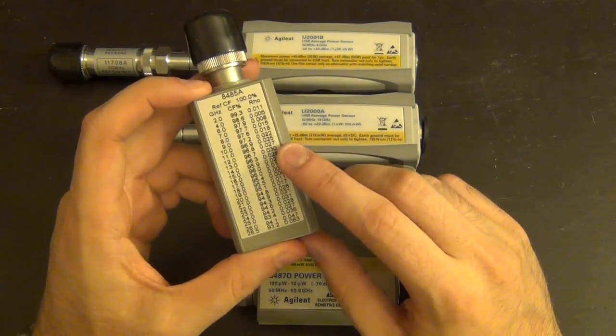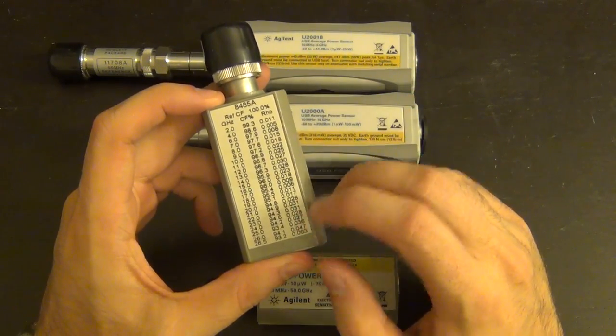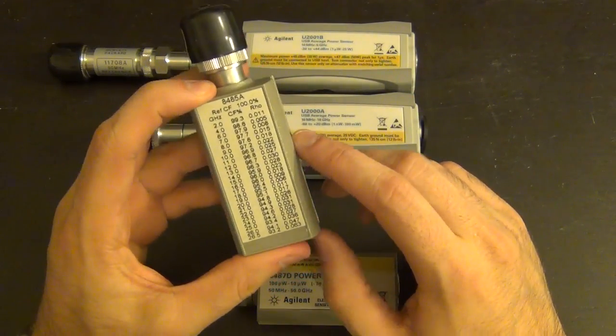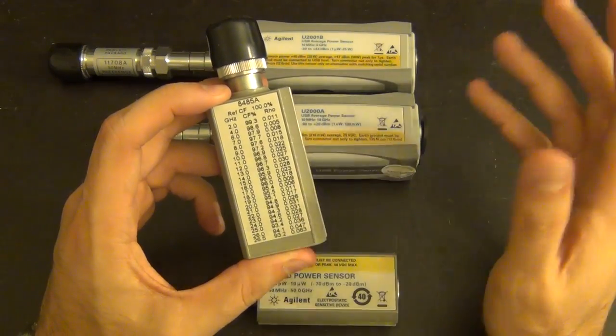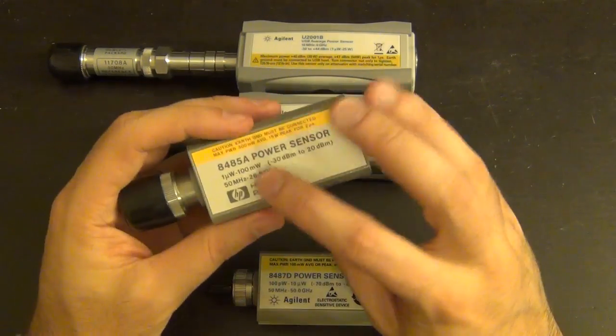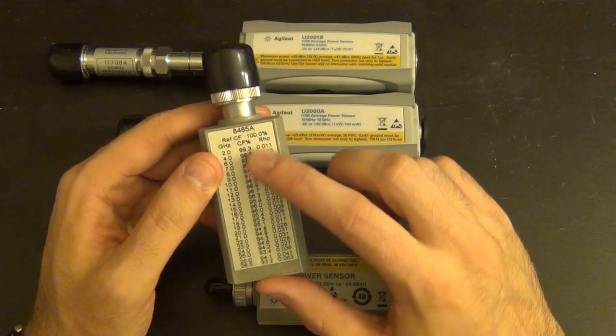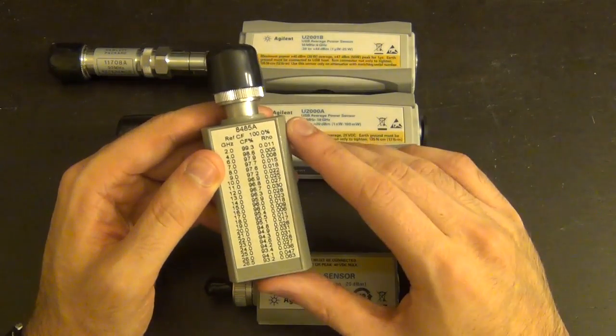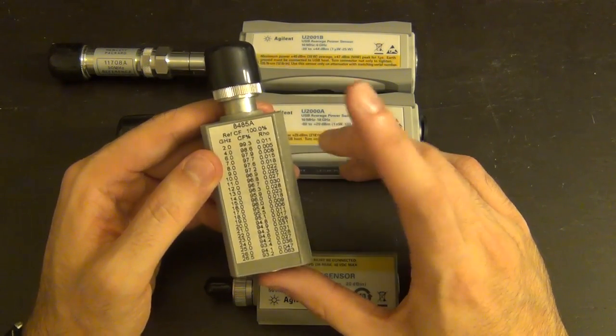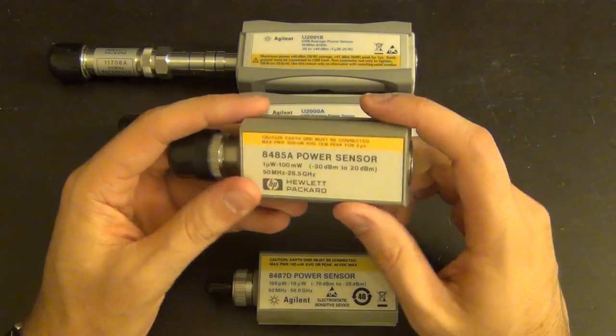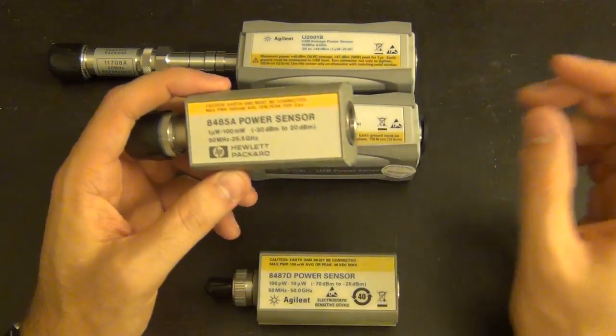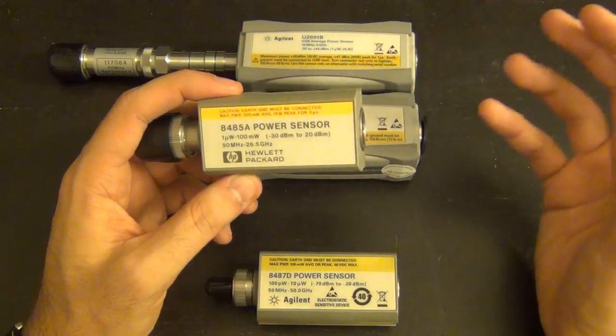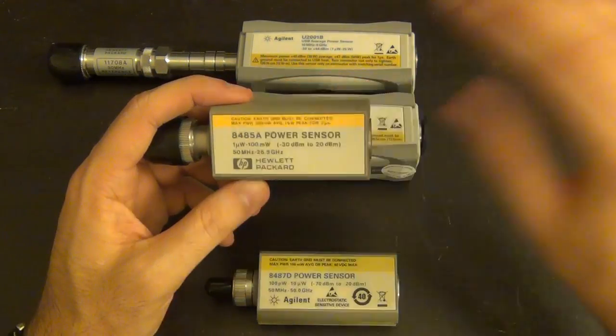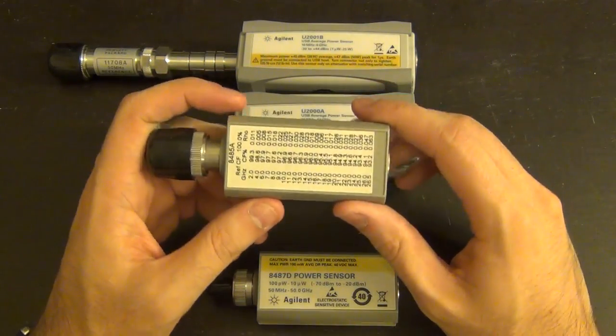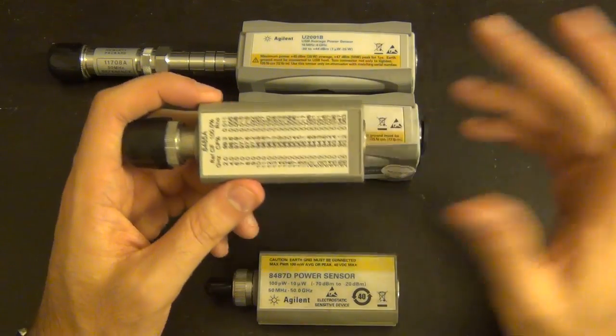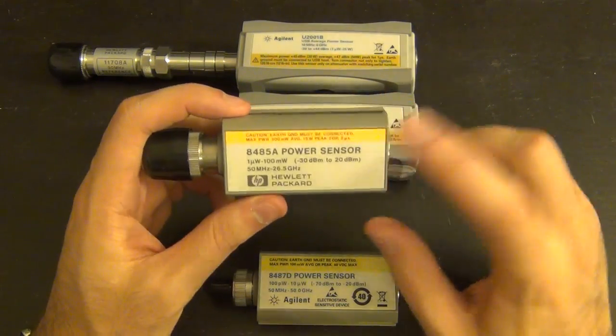The calibration table with all the coefficients is printed at the back, done at the factory level for each individual sensor separately. You then load this table onto the power meter so that when you set the frequency, it knows what correction factor to apply and gives you the correct power reading. For the newer E-series power sensors, once you plug these into the power meter, the data is automatically transferred serially, so you don't have to type it in. Otherwise you have to enter it manually - you can save it and unload it later when you switch sensors.